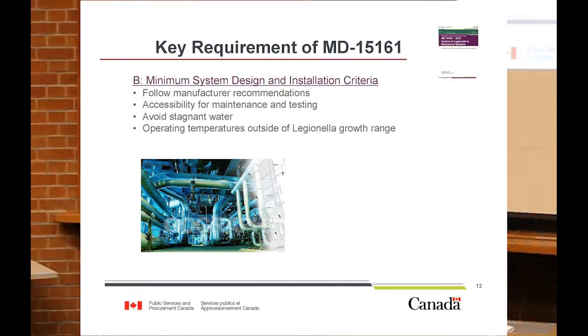On the design and installation side, there are additional specific requirements for some of the various system types, but basically we're looking at following manufacturer recommendations and ensuring accessibility for maintenance and testing of systems. This is critical because when controlling Legionella growth, you have to be able to do your maintenance on the systems—avoiding stagnant water, and where possible, operating temperatures outside of the Legionella growth temperature range. That's not always possible, especially with cooling towers, because they operate right in the middle of that range.